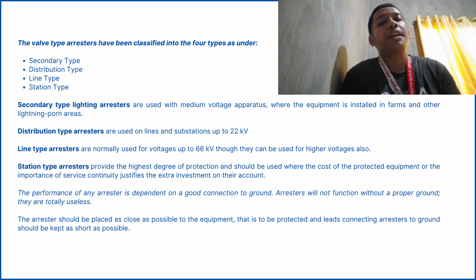First type is the secondary type arrestors. These arrestors are used with medium voltage apparatus, typically in farms or areas prone to lightning. The second type is the distribution type arrestors. It is commonly used on distribution lines and substations up to 22 kilovolts. The third type is the line type arrestors. It is suitable for voltage up to 66 kilovolts and sometimes even higher. And the fourth type is the station type arrestors. These provide the highest level of protection and are used in substations or power stations where equipment cost and service continuity are critical.